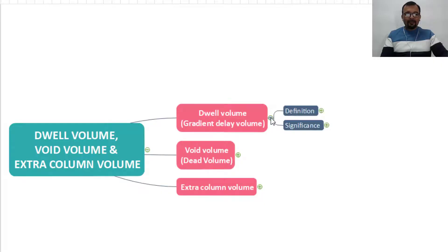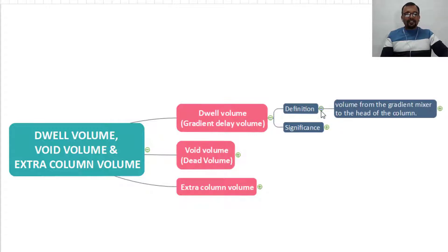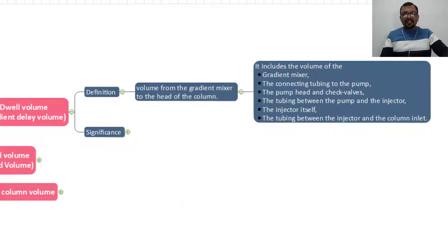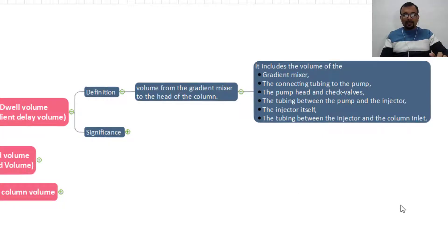Let us begin with dwell volume. The dwell volume is the volume from the gradient mixer to the head of the column. It includes the volume of the gradient mixer, the connecting tubing to the pump, the pump head and check valves, the tubing between the pump and injector, the injector itself, and the tubing between the injector and the column inlet.